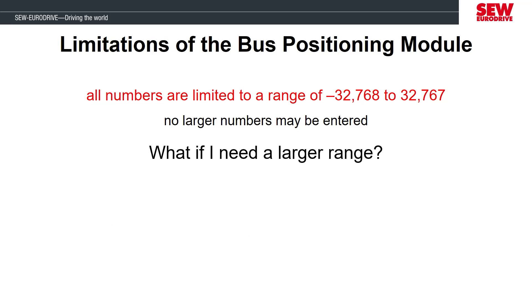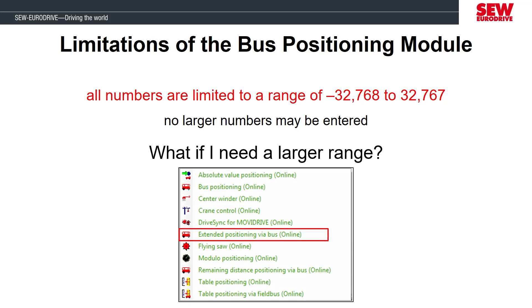If a 16-bit word is too small for the value range you need to send over the fieldbus, there is another application module called extended positioning via bus. This application allows you to set a 32-bit position instead of a 16-bit position by combining two 16-bit process data words into one long process data word for the position. It also adds additional process data words for the acceleration and deceleration time, bringing the total to six process data words in and out of the MOVIDRIVE. We won't be demonstrating this module, but it's available if you need a larger position value or the ability to change acceleration or deceleration via process data.